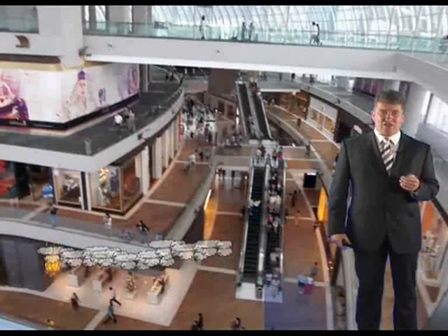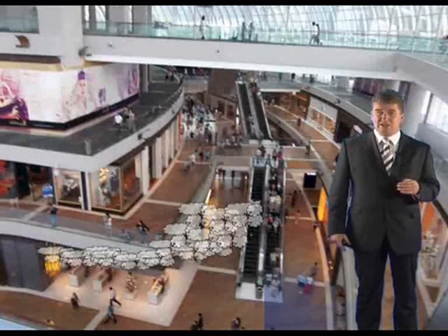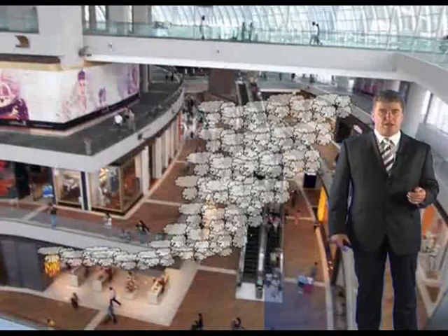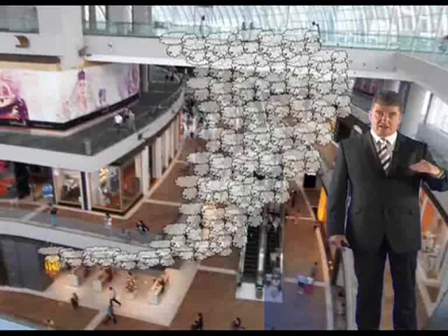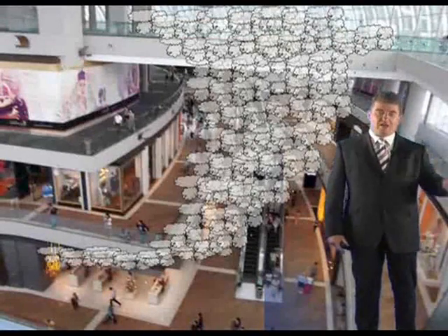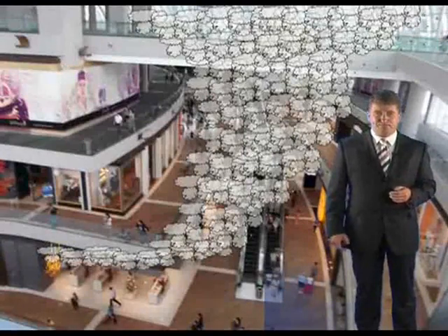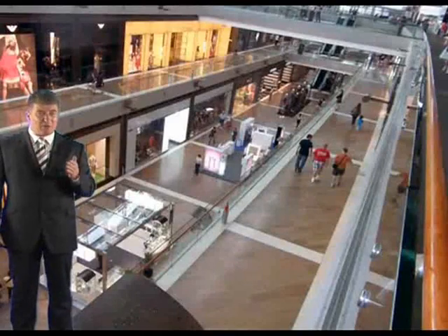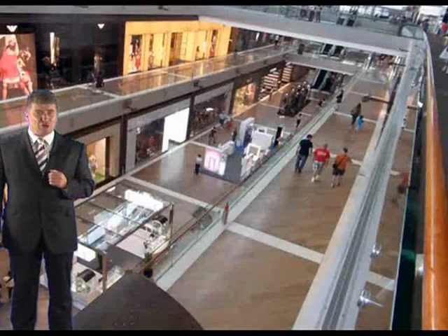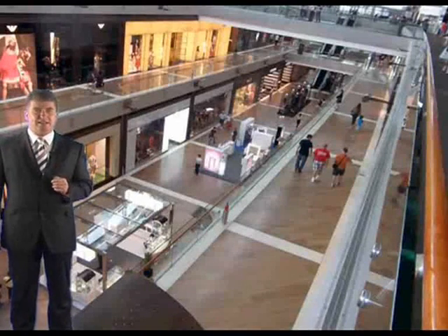However, there are situations where the smoke may travel some distance before being extracted, and this is known as a complex plume. For example, a shopping mall is a good example of one, where the fire starts in a shop, comes out of the shop, travels down the balcony, hits a spill edge and reaches an atrium. That is called a complex plume, and obviously there's more calculations involved and a lot more smoke entrainment. Now, a good example of a complex plume, as I said, is a shopping complex or a shopping centre, and this is what I'm going to go through now, the principles of shopping centres.